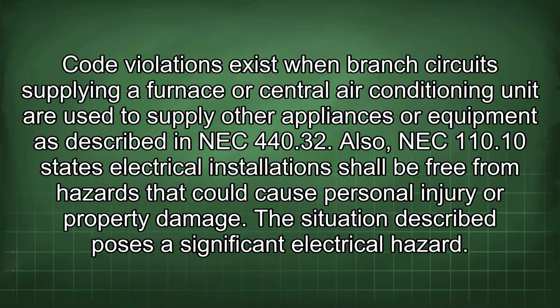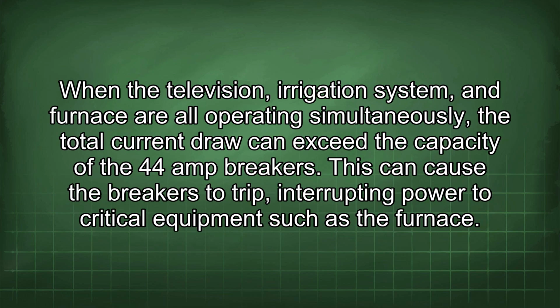Code violations exist when branch circuits supplying a furnace or central air conditioning unit are used to supply other appliances or equipment, as described in NEC 440.32. Also, NEC 110.10 states electrical installations shall be free from hazards that could cause personal injury or property damage. The situation described poses a significant electrical hazard when the television, irrigation system, and furnace are all operating simultaneously.